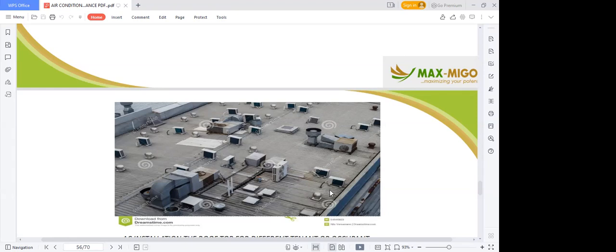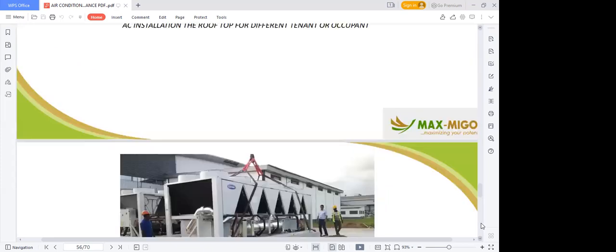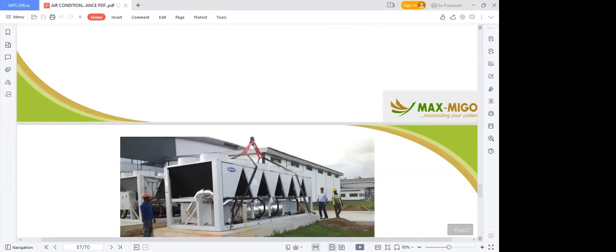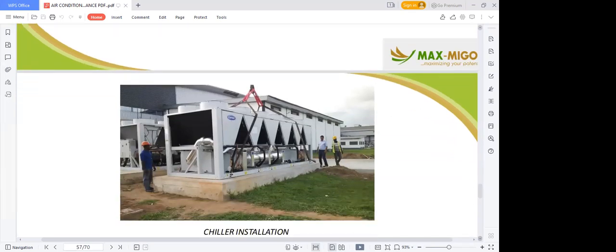It might not be a good design, but the beauty is that it is on top of the roof. So nobody sees it except you or your technician. Then this is one of the units I also delivered to one of our clients. So if it must be a chiller system, ensure that there's a plinth, which is the base. Then the base will have a vibrating pad.